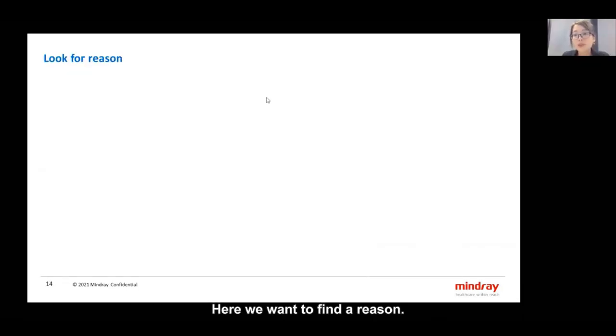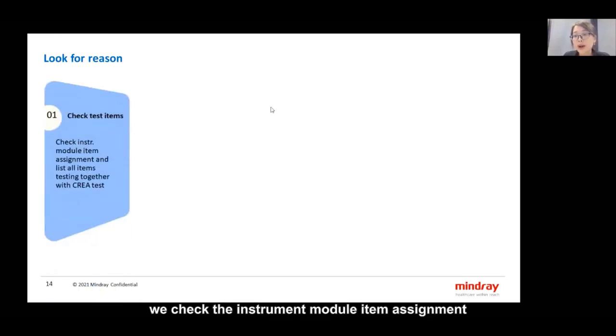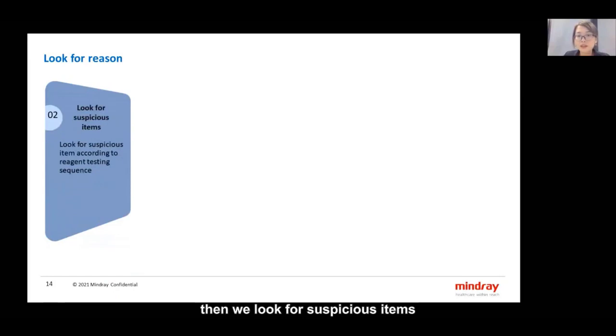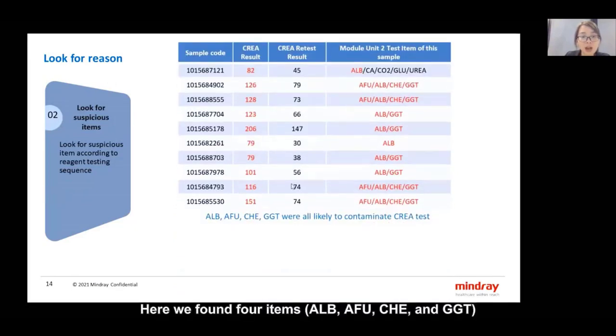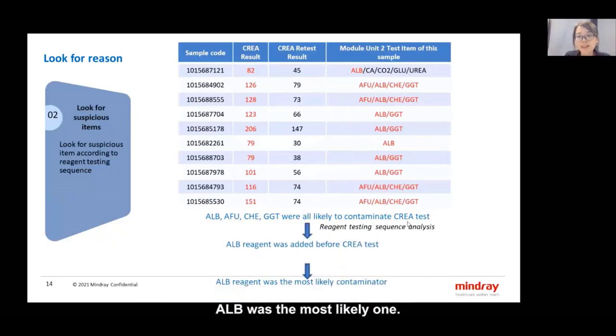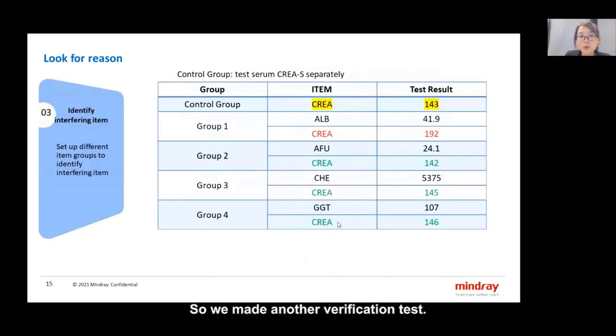Here we want to find the reason. Firstly, we check the instrument module item assignment and list all items testing together with the creatinine test. And then we look for suspicious items according to the reagent testing sequence. Here we found 4 items were likely to contaminate the creatinine test, and ALB reagent was the most likely one. So we made another verification test.